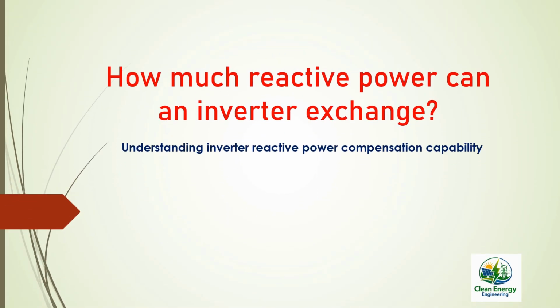Have you ever heard a 100 kVA inverter is generating 100 kVAr of reactive power and you are thinking, is it really true? So how much reactive power can an inverter generate or absorb? Is it limited or unlimited or restricted? And what is the maximum capacity an inverter can generate or absorb the reactive power?